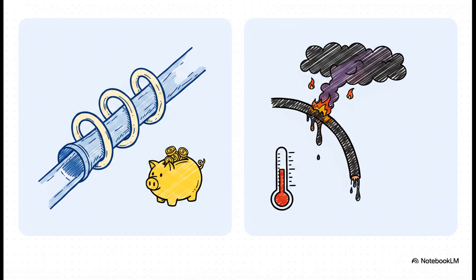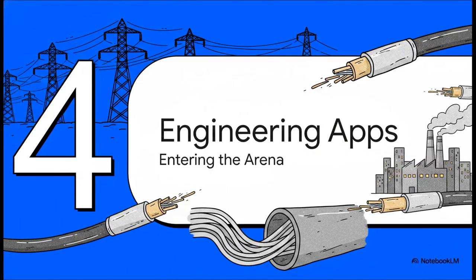However, its weaknesses are definitely severe. It melts above 70 degrees, its high dielectric losses make it basically useless for high voltage, and, this is a big one, if it actually is subjected to an active fire, that same chlorine causes it to emit dense black smoke and toxic, corrosive hydrochloric acid fumes. So the crucial point is, where do we actually use them?